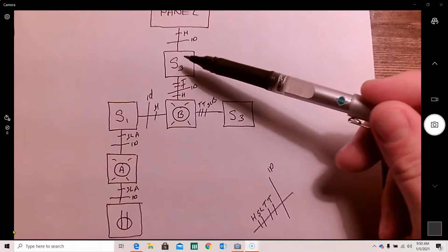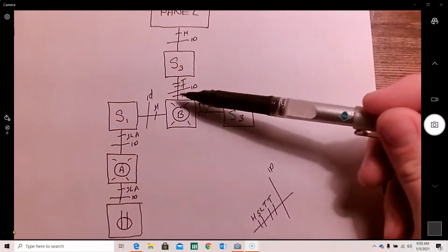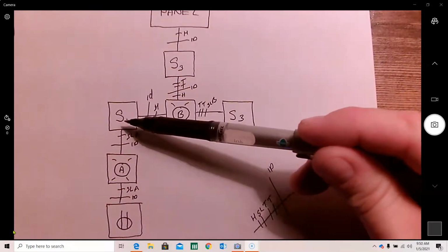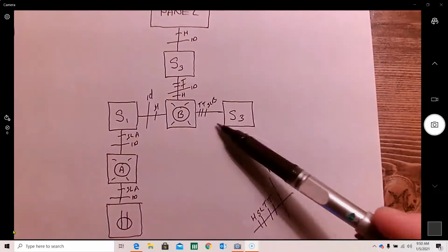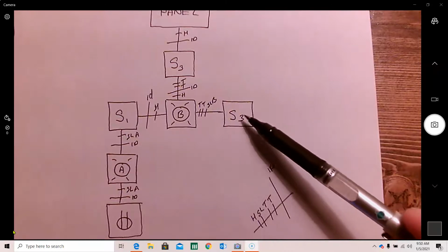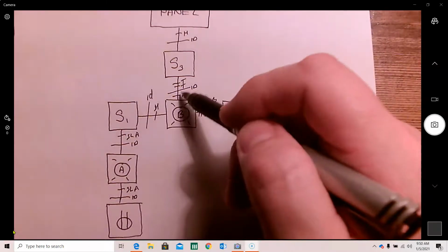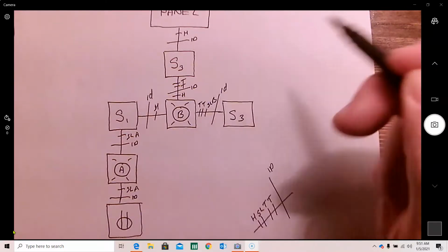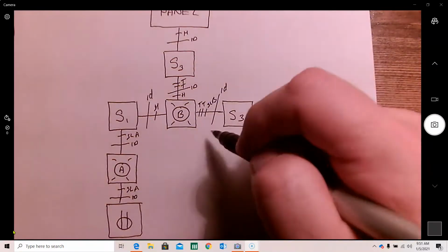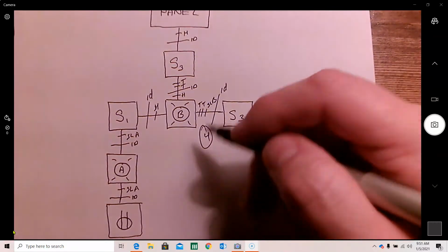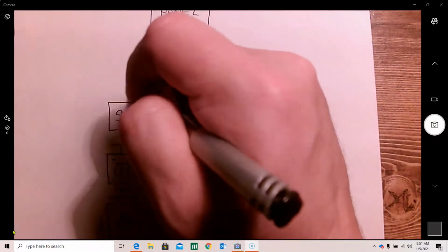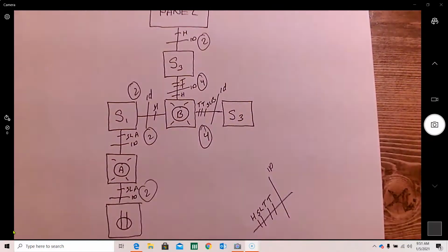So I already have an identified in here. That's the identified traveling through. It's already located in there. I have an identified located in here already because it's traveling through. But here, I don't have an identified available for this switch. So I need to tap off in here and bring an identified into this switch here. So I just put an identified there. All right. Then you can say, okay, there's 4 in this guy. There's 4, 2, 2, 2, and 2.